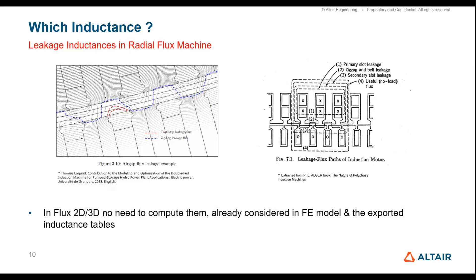Let's look at leakage inductances, with focus on radial flux machines. When considering the cross-section of the machine we can see leakage inductances on the stator slots, and if there are slots on the rotor, leakage inductances there as well. This image is extracted from Alger's book, and from a PhD thesis we can see a beautiful picture of zigzag leakage magnetic flux giving the zigzag leakage inductance. There is also leakage flux between the two sides. These are difficult to compute, but the good thing is that when using finite element computation, all these leakage inductances are already taken into account.